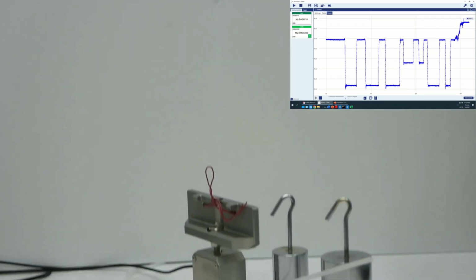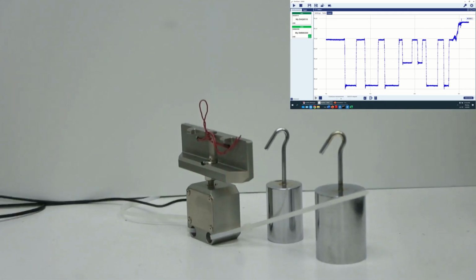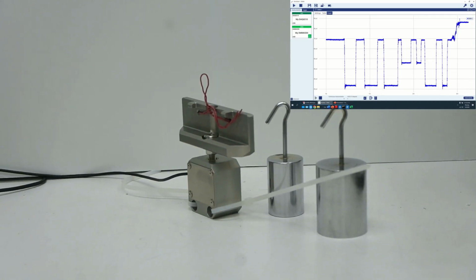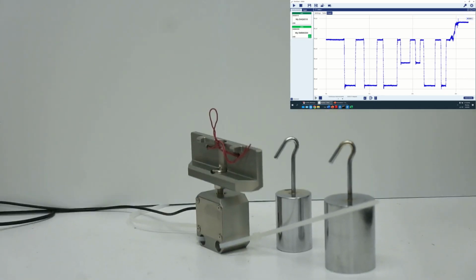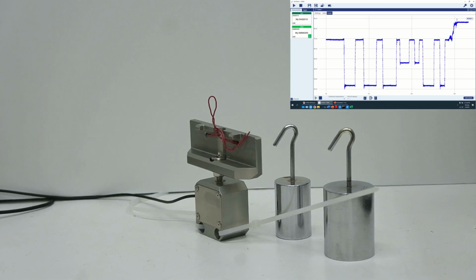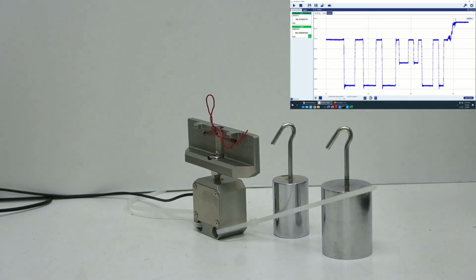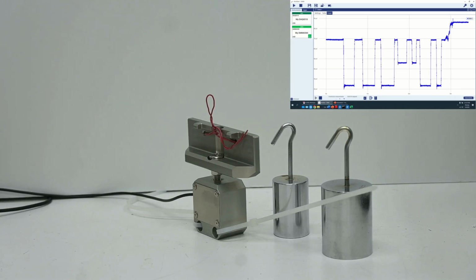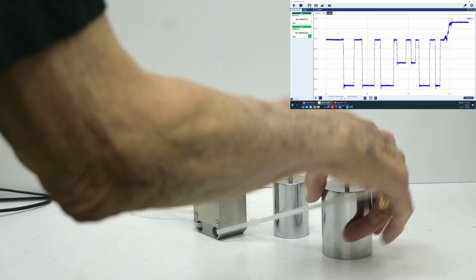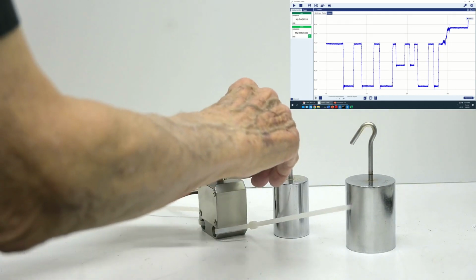I will move the camera down so we can see the bench. Notice on the graph with the sensor on the bench, the no-load voltage has changed to about 86 microvolts instead of 69 microvolts. This happens when it is hanging. Part of the cell clamp is hanging from the sensor. With it on the bench, part of the clamp weight is on top of the sensor.